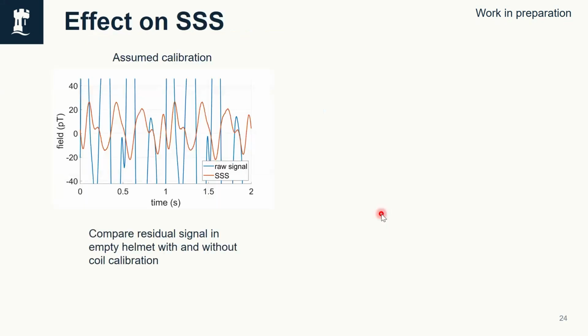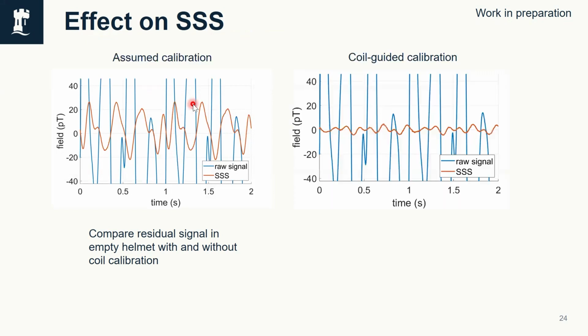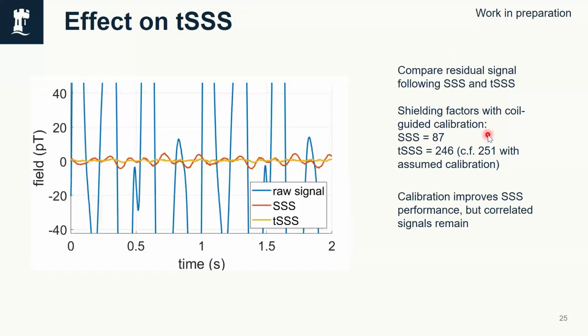But just looking at the effects on SSS, if we use the assumed calibration, we already saw we had about 20 picotesla. If we use our coil guided calibration, it does a much better job. So we're getting around a 10 times improvement in calibration. And I'll just skip that, but TSSS still helps.